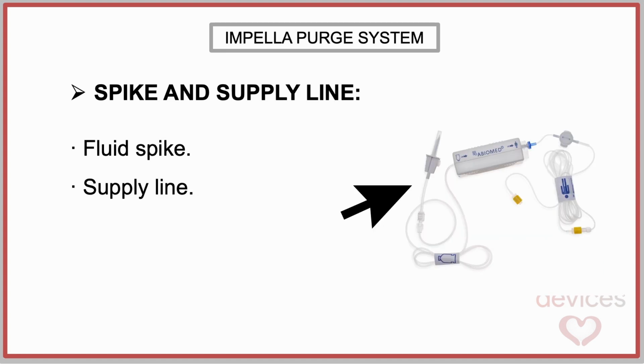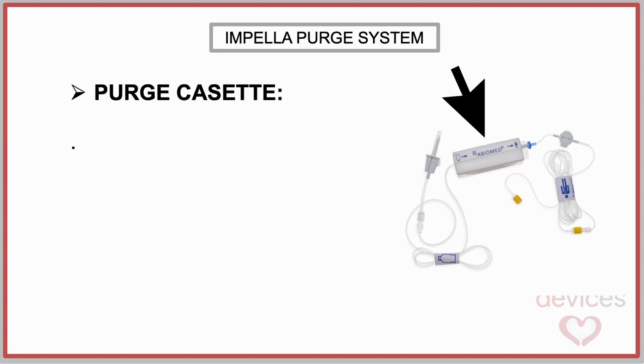The purge fluid bag is hung above the automated Impella controller, and it is connected via a purge fluid spike, which pierces the bag to draw fluid, and a supply line that carries fluid from the bag to the internal mechanism of the cassette. The core of the system is the Purge Cassette, a single-use accessory that mounts on the front of the controller.